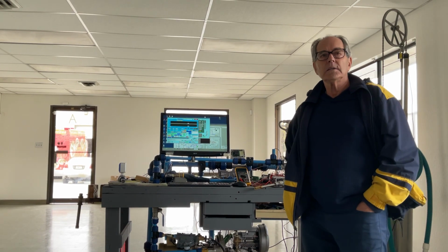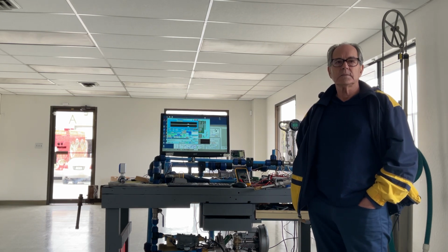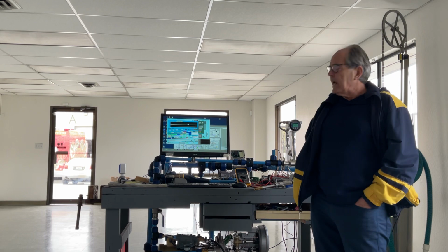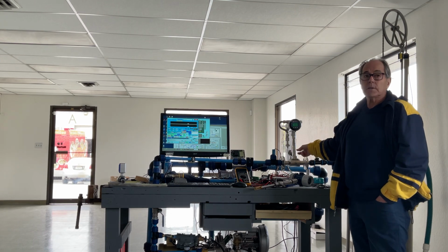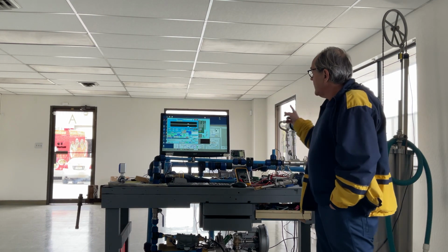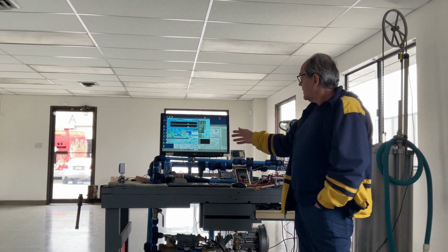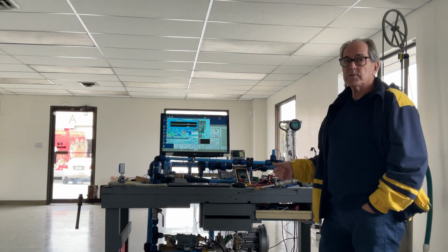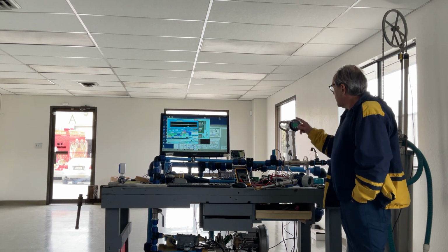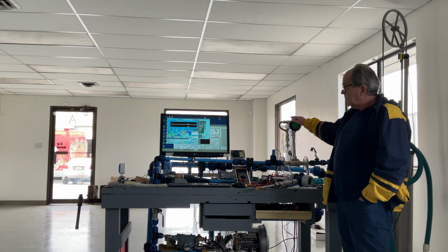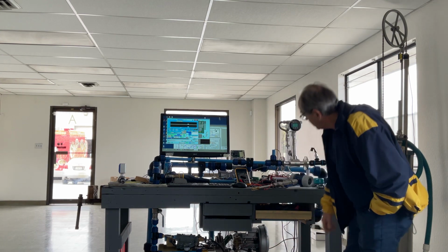Yeah. This is basically a really, really good calibration system that we can use to find and subtract out any of the errors in the flow meter. And I would say this is a method of characterizing a flow measuring instrument. So it characterizes and it speaks in its native tongue, which we've made standard cubic feet per minute, that can be converted to any unit at any reference temperature and any reference pressure, and then take that characterization, program it inside of any device, this device or this device or the other one.